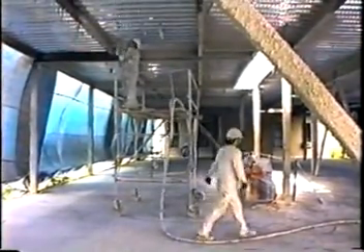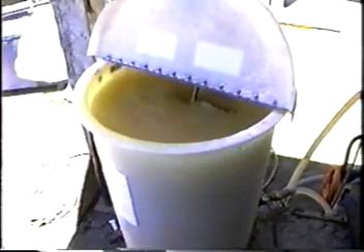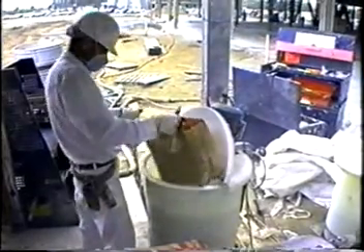Rolling scaffolds should be provided for applications that are not accessible from the floor. Scaffolding should be in accordance with all OSHA requirements. CAFCO QWIK-SET is an accelerator that is added to CAFCO 300 to reduce the set time, and QWIK-SET is applied by using a chemical metering pump which conveys the solution through a hose to the wet mix nozzle where it is mixed with the 300 slurry.